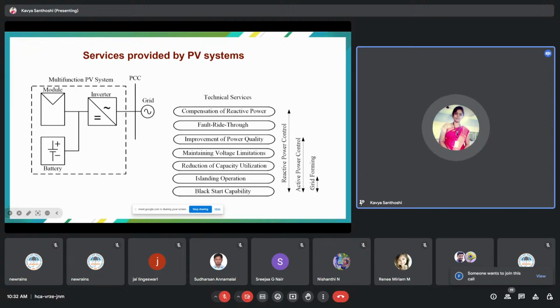Islanding is a term very popular in microgrids, because when we operate a smart grid and microgrid, we operate in islanding mode as well. Islanding means that although the grid is not connected, if we observe this figure, we have a connection to the grid from the inverter. But in case it is not connected, there is still power flow in this multifunction PV system, and the components of our power station are still powered. That is islanding mode. We are not connected to the grid, yet the components are powered. So workers need to be careful and warned about the powered devices so they can take precautions accordingly.